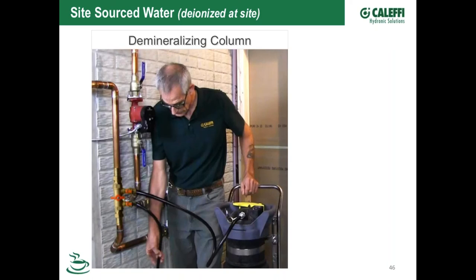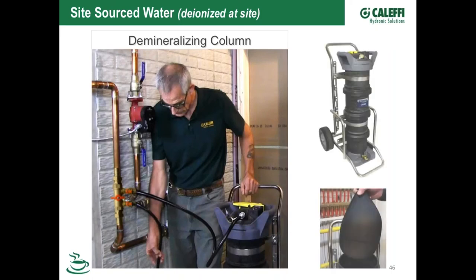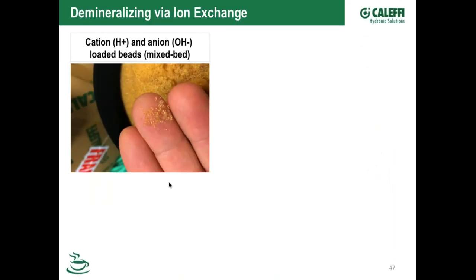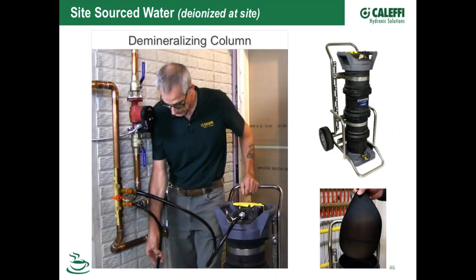So yeah, you do have to pay attention to those low water probe type cutoffs. Hey Bob, this is Mark. With several manufacturers of low water cutoffs that we tested using demineralized water, 10 parts per million was pretty much the common cut-in and cut-out point where those conductivity type probe low water cutoffs work.